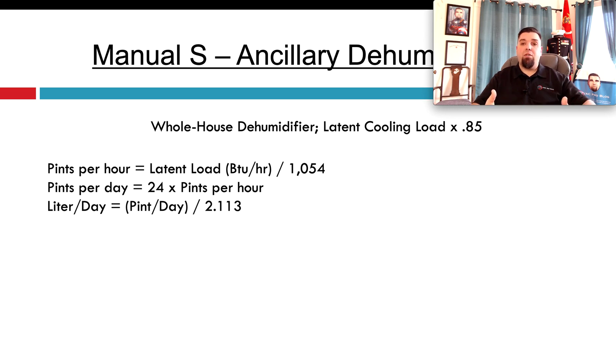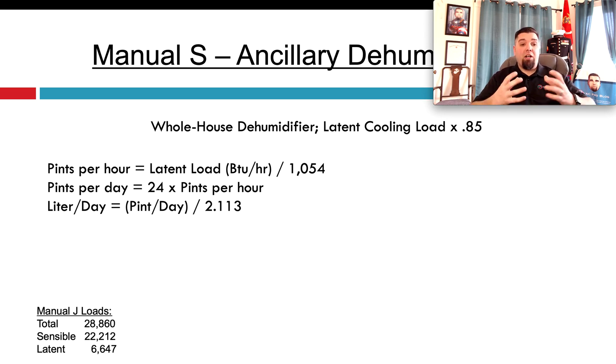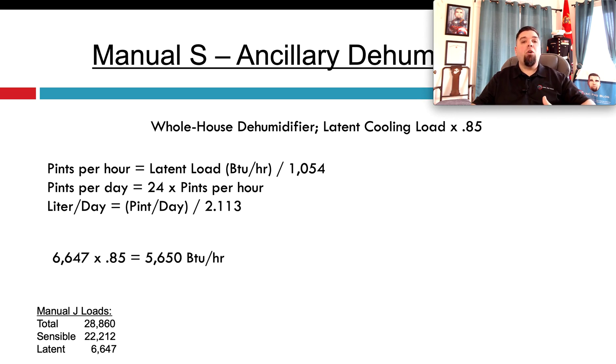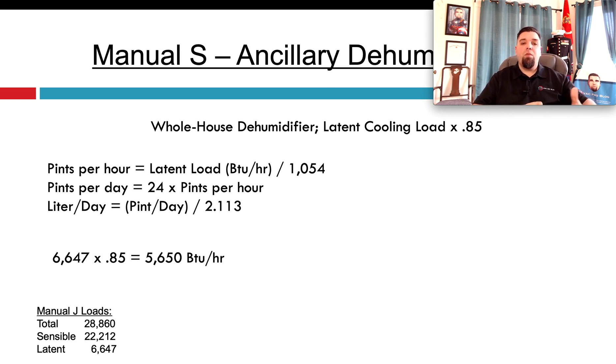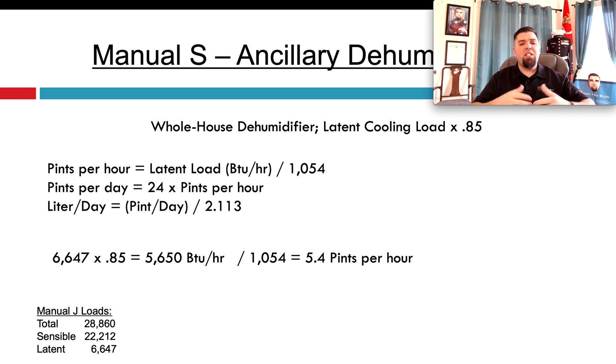That latent load is in BTUs, so we need to convert BTUs over to pints per day or liters per day, because that's how we rate dehumidifiers. Here in the United States, manufacturers rate them in pints per day. Taking the fictional load calc from earlier, I need 6,647 BTUs. We take 85% of that, which is 5,650 BTUs — that's our target. We then divide by 1,054, the constant to convert BTUs per hour to pints per hour, giving us 5.4 pints per hour.